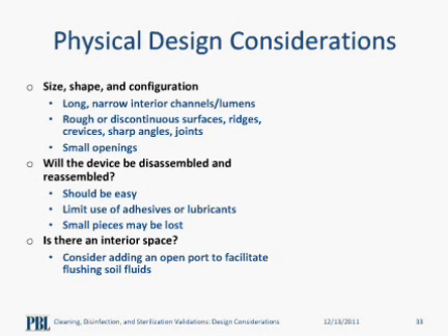We have to avoid or at least limit the use of additional agents in reassembly, such as adhesive chemicals or lubricants, which later become toxic or harmful to users. If a device cannot be disassembled but has inner channels to which the patient's blood or other body fluids can gain access, it is important to include an opening or a port that facilitates flushing through the inner channels. Brushing should also be taken into consideration during the designing process of the device. It is beneficial to design a brush appropriate for the device for ease of proper cleaning.